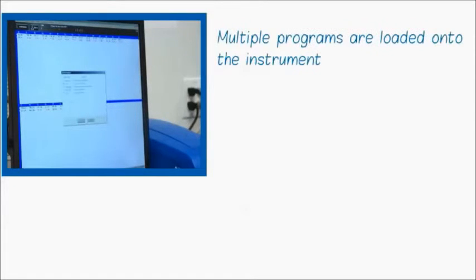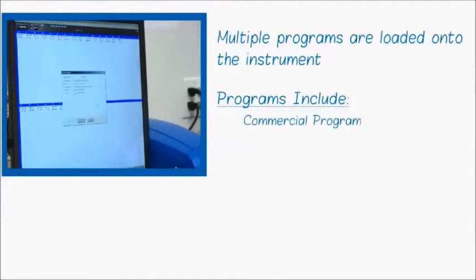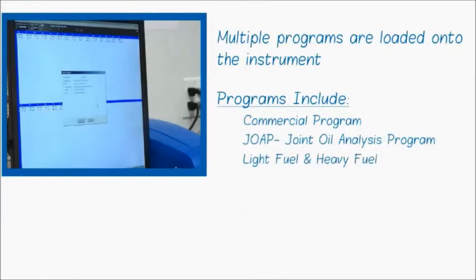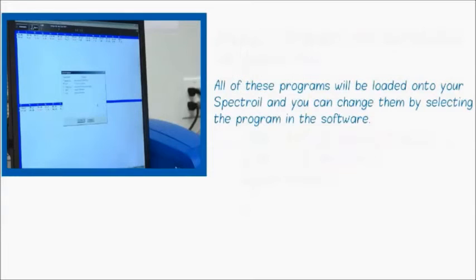If I go to File, Open, I can see all of the programs which are loaded onto my instrument. A program might be the commercial program, the JOAP program, for doing light fuel or heavy fuel, or for doing glycol and water. All of those programs will be loaded onto your Spectroil, and you can change them just by selecting the program in the software.